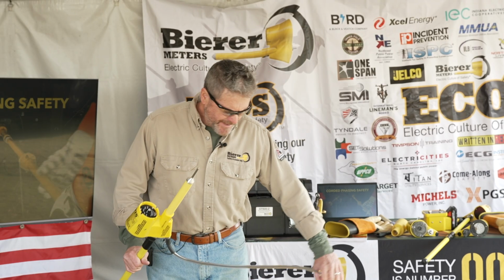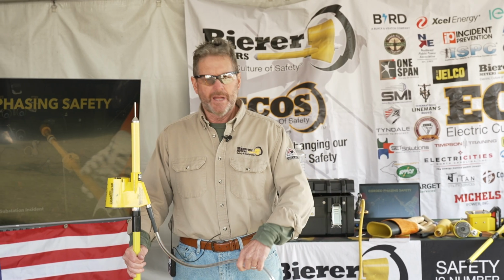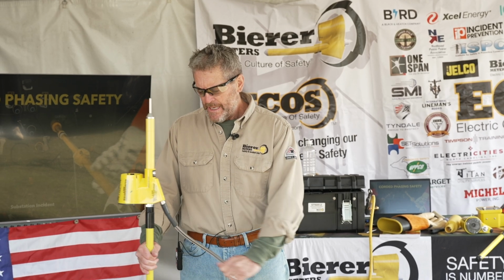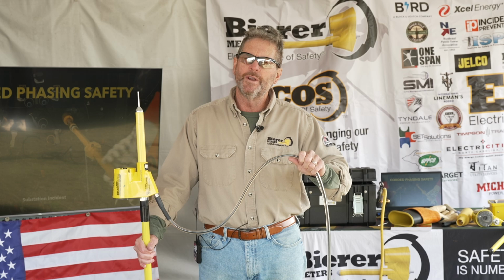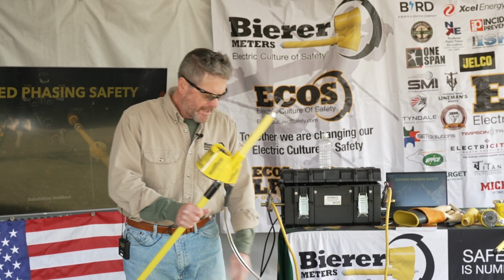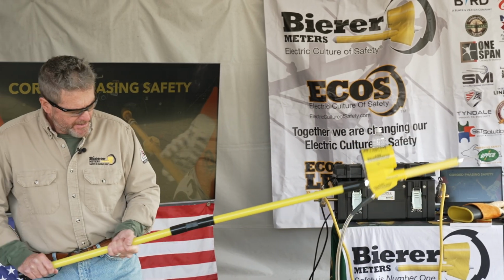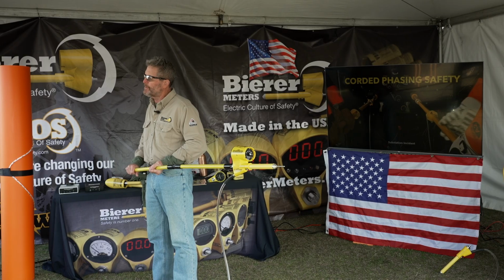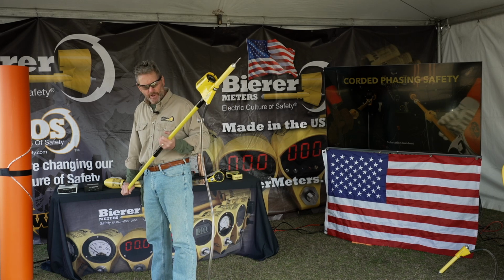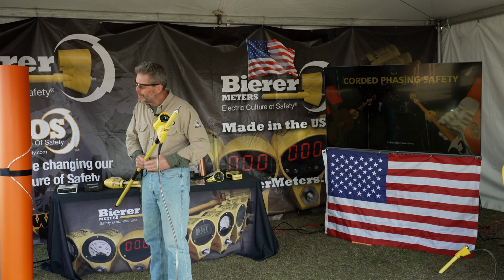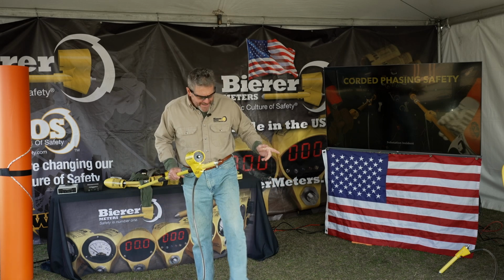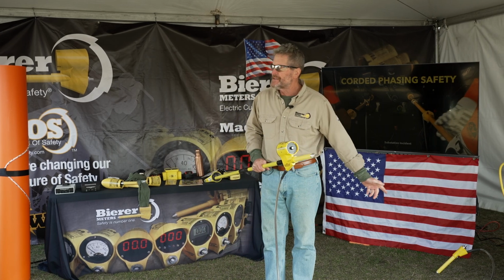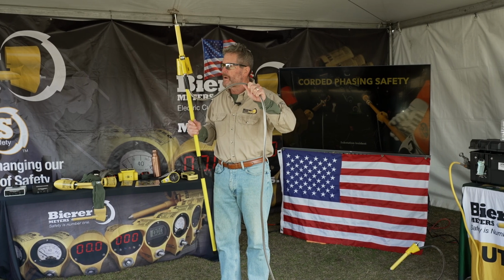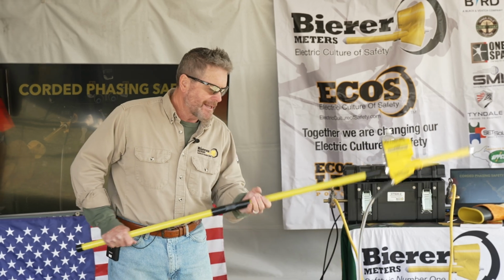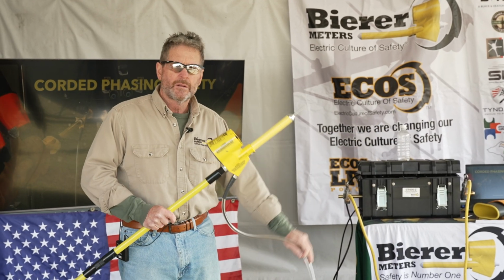So the cord phasing safety - remember that potential, that piece of potential, and that current is flowing through the cord. When you're using these cords, always keep them 36 inches away from your foot, your leg, your body, even if you're in the bucket truck. Always, because that current is flowing through that. It's energized going to that secondary probe, whether the secondary probe is going to ground or to another phase, it's energized. So the cord is part of the tool. Remember, keep away, keep your air dielectric - same thing. Get away from the cord, same thing.